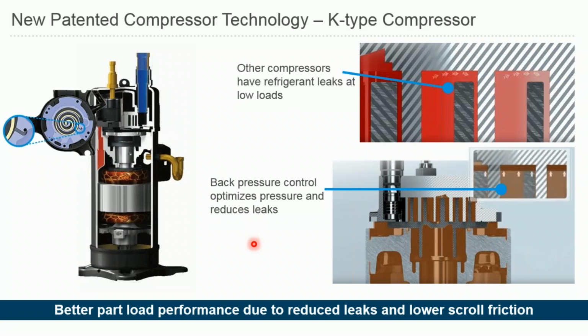So with that check valve you saw on the previous slide and the larger vapor injection hole, at low load operation, the system can detect the pressure imbalance and send some more vapor or refrigerant back to the lower side of the scroll configuration, to this side. When that happens, it pushes that orbiting scroll to the top side, reducing this gap that you would typically see with other compressor designs. So that makes the compressor much more efficient, especially at low load operations.